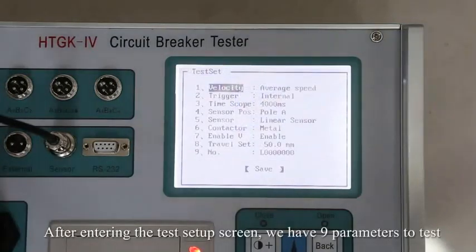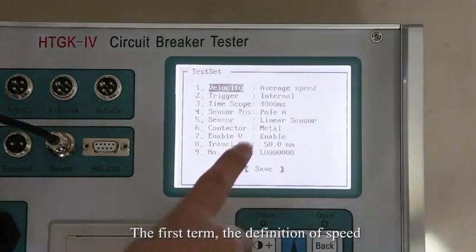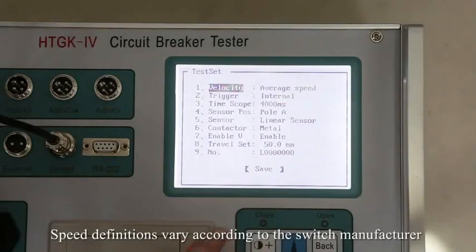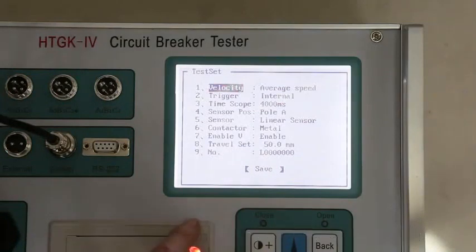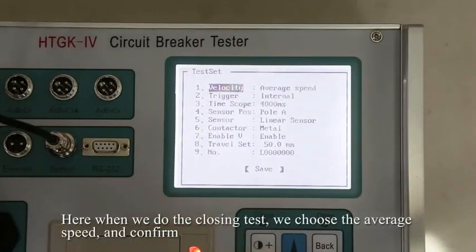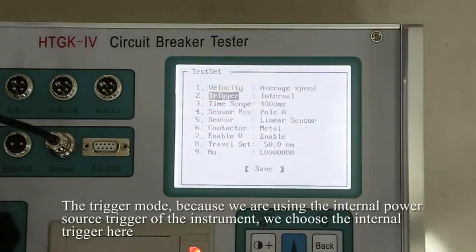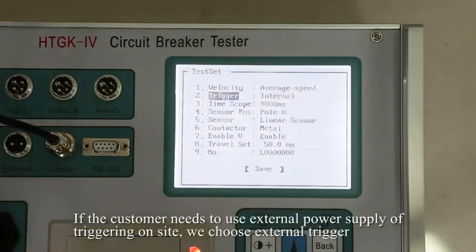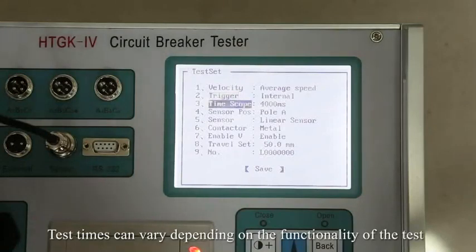After entering the test setup screen, we have 9 parameters to set. The first item is the definition of speed. Speed definitions vary according to the switch manufacturer. Here, when we do the closing test, we choose the average speed and confirm. The trigger mode: because we are using the internal power source trigger of the instrument, we choose the internal trigger here. If the customer needs to use an external power supply for triggering on site, we choose external trigger. Test time can vary depending on the functionality of the test. Here we choose 250 milliseconds.